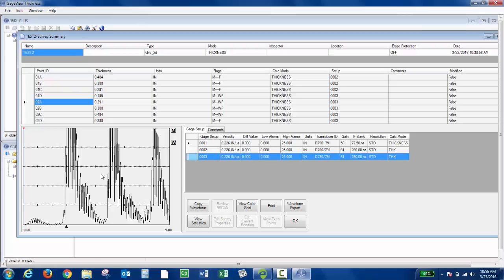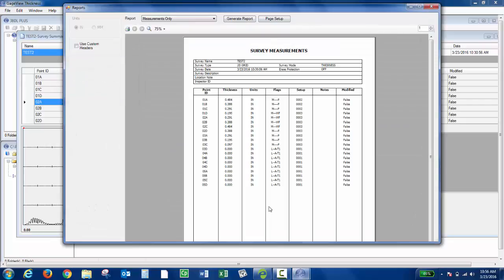To print a survey report, you'd first want to open the survey file like we did, and then you'd click Print. This is just showing me my IDs and my thickness values. If I also wanted to show some waveforms that were saved...